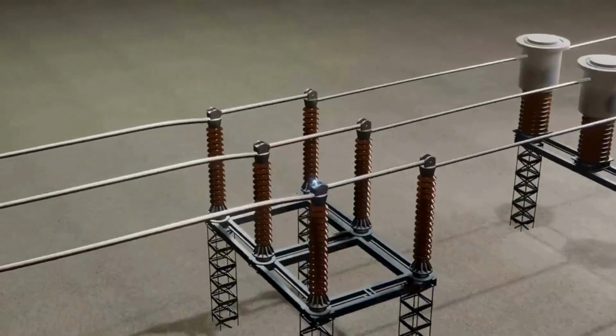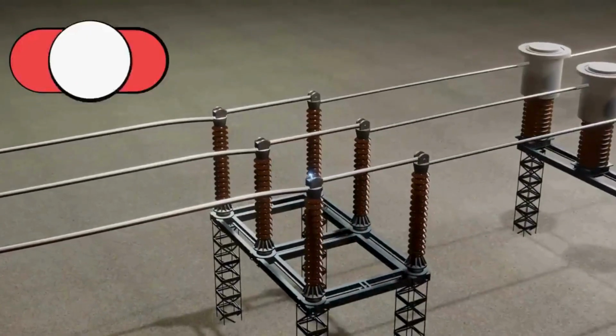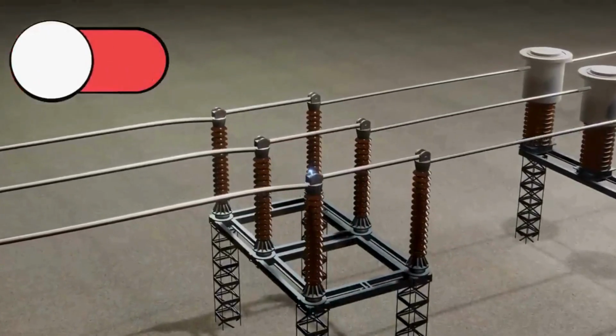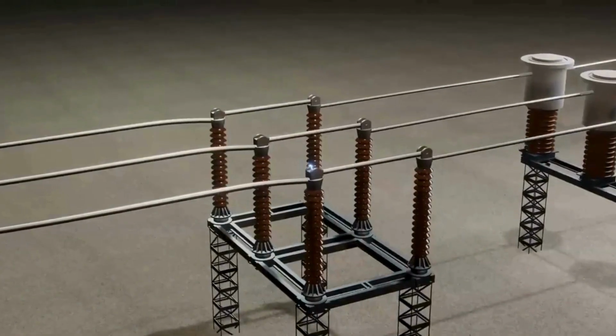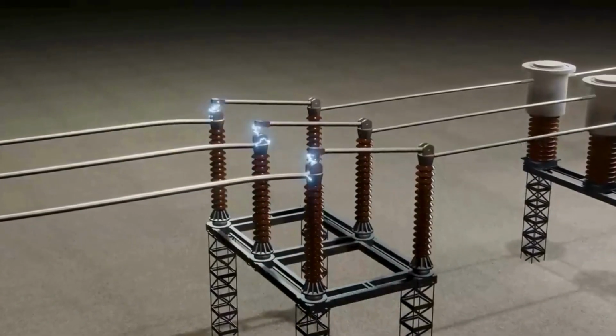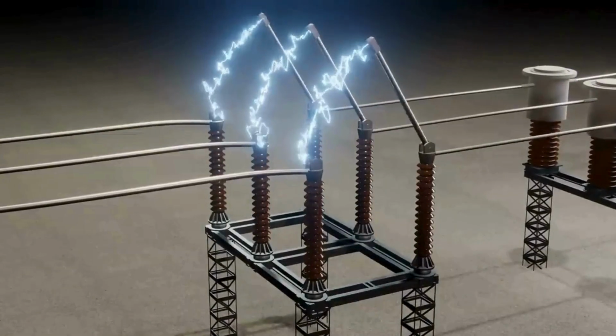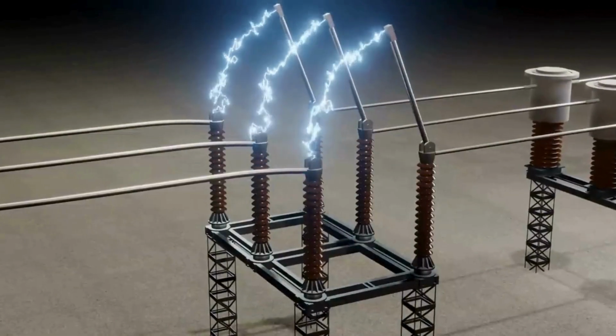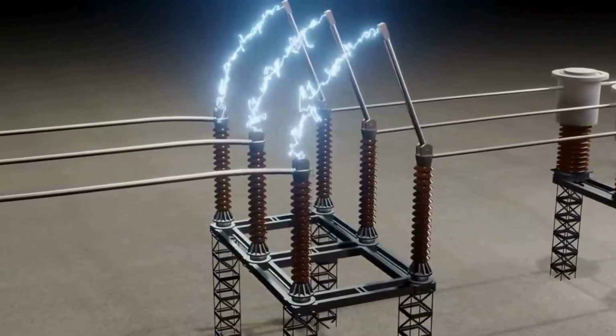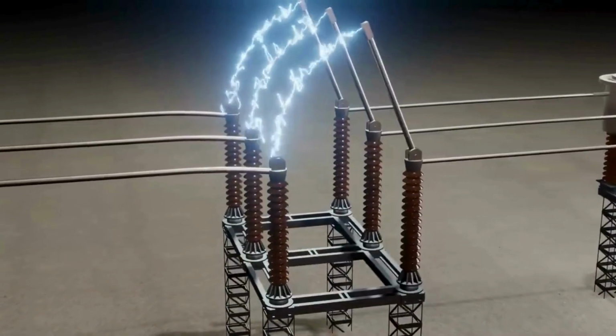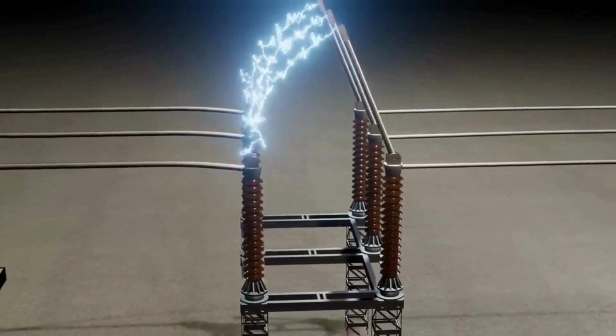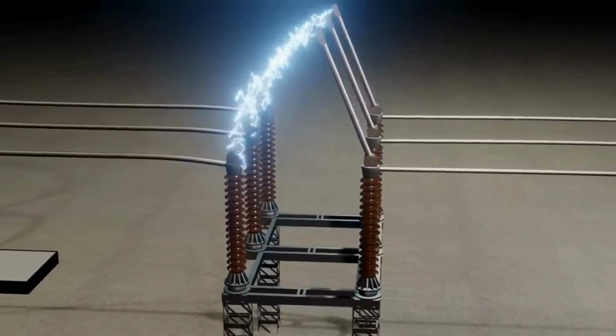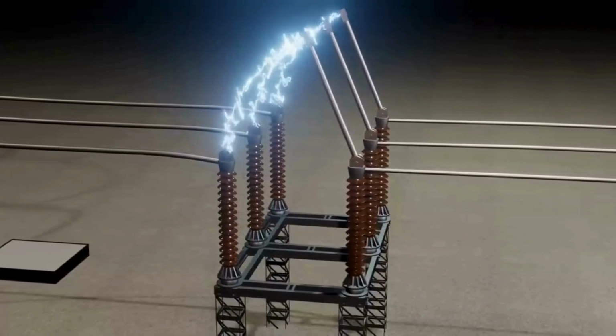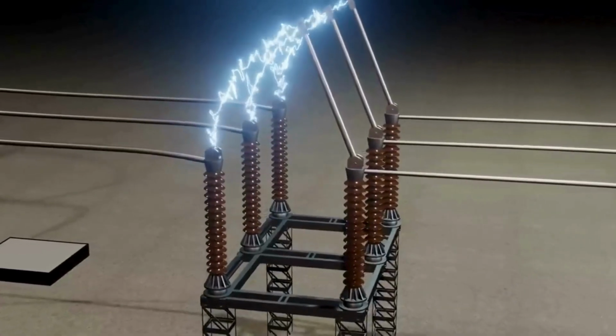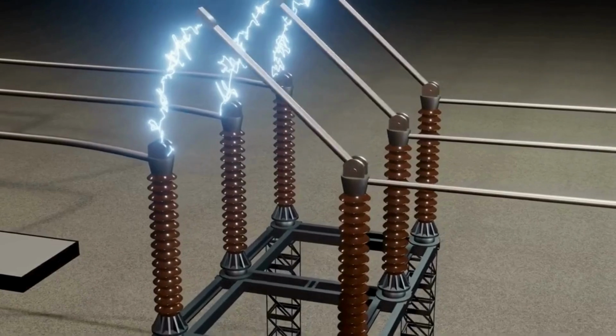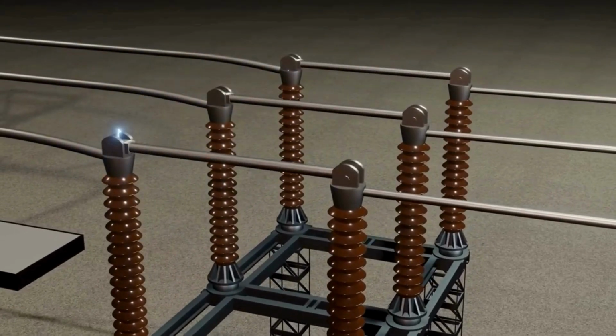This is an isolator that is attached to close the 400 kV line, which works exactly like our home switch. But when the isolator is removed to close the line, you will see that we have removed the isolator connection. Still, there is a connection made with such a heavy sparking through the air. Now the contact of the isolator will start melting with such heavy sparking. The line is 400 kV now, the voltage of the transmission line is up to 1100 kV. So the isolator is definitely attached to the line, but the on-load line cannot be broken.